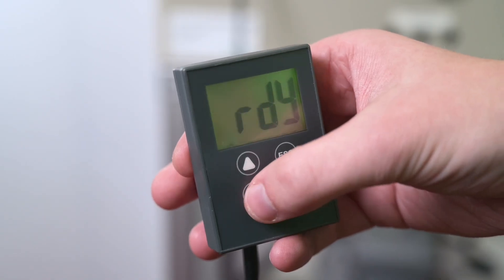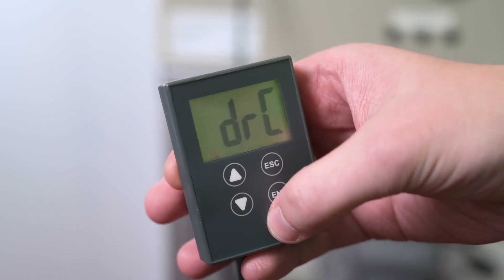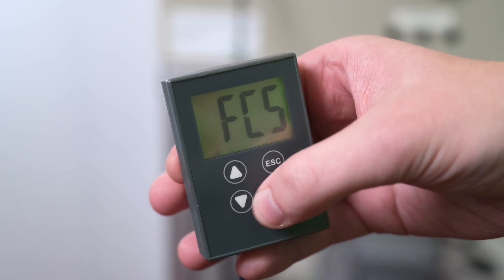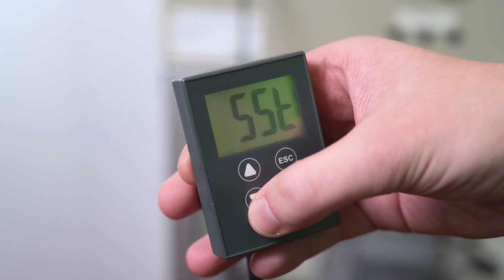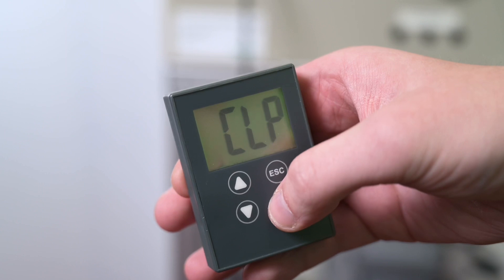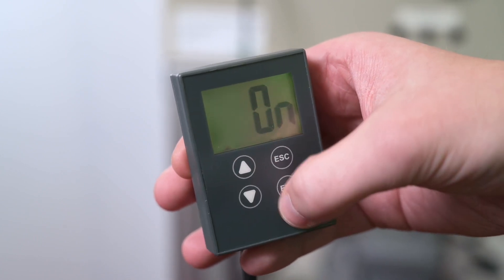First, we are going to set the parameter torque control CLP. By default, the torque control is set to ON. Otherwise, if torque control CLP is set to OFF, starting and deceleration are controlled by voltage variation.